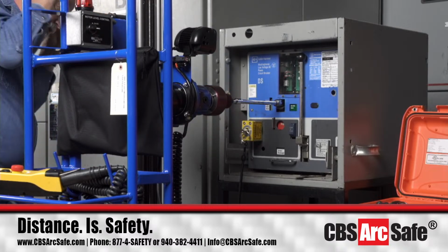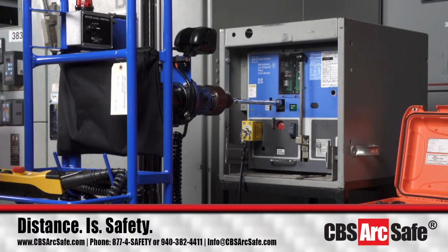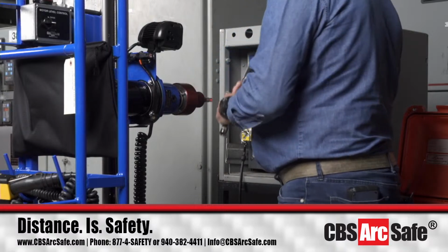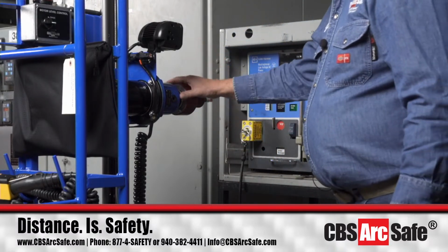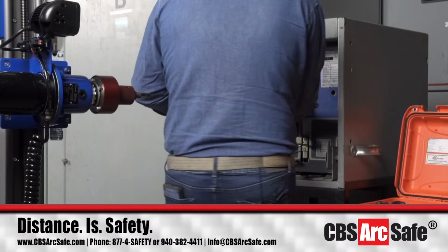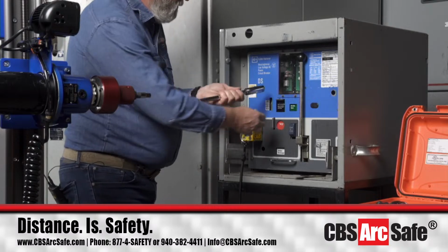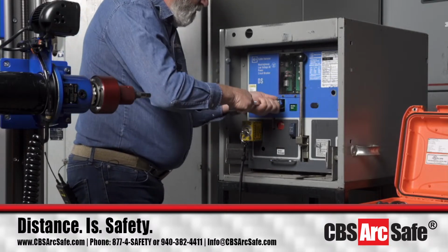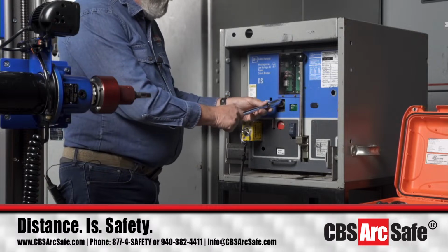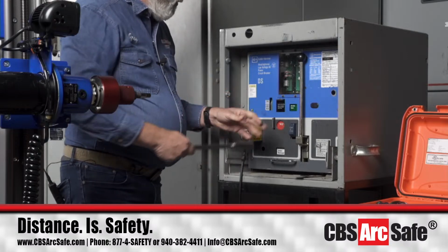Let me just look at something here. Let me get to the other side here for a second. There we go. But you see that the door still closes. And if I can do this by hand, I don't know if I can do it, I'm going to try just to show you what I'm really talking about here. So if I come back like a turn and a quarter there, it's still closed. If I come back just a little bit more, the door's not going to close. So if the door closes properly, it means the breaker's in the connected position as far as it can tell, and it's going to be able to operate normally just like this.